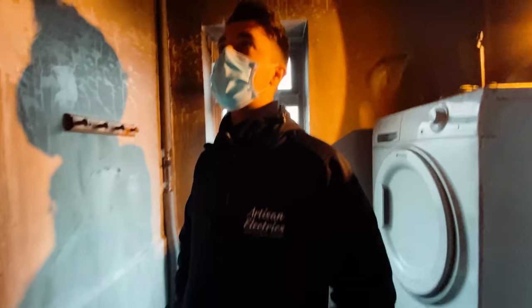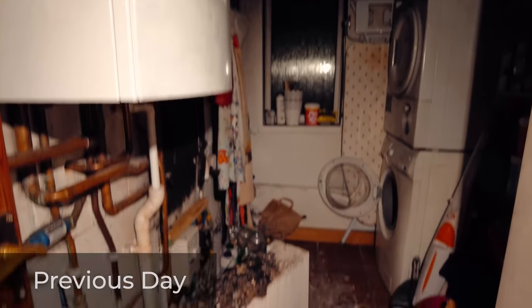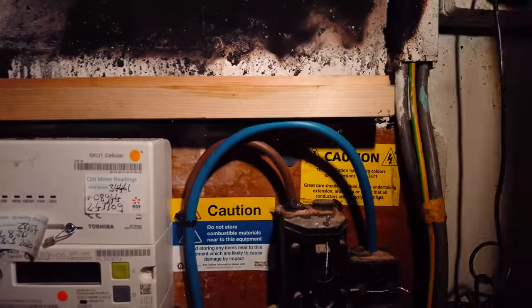Corey was the brave hero who came out last night to investigate. So I've just arrived at the site of the fire — it's actually really quite severe. Thankfully for the customer, it's quite a miracle: the main fuse was blown, it was only a 60 amp 1361 fuse. Missed all the gas pipes and everything. The boiler is just here and it is absolutely cooked. We've been called in to ascertain where the fire started. I think it started inside that board — that board looks smoked. You can see it's spread throughout the room quite severely.